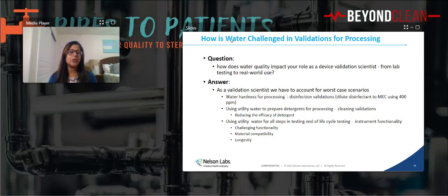Some things we take into consideration when doing disinfection validations: high-level disinfectants, let's say a Cidex or Cidex OPA used over time, with a 14-day shelf life—we're diluting that disinfectant with 400 ppm water. Think about the very hard water being over 180 ppm. We're diluting this disinfectant at 400 ppm, so you can see how ineffective this disinfectant is going to be.